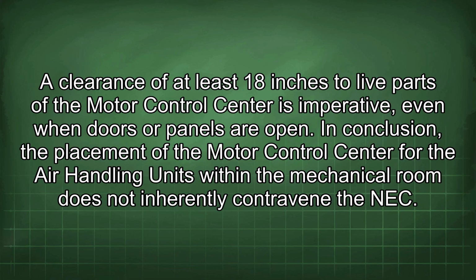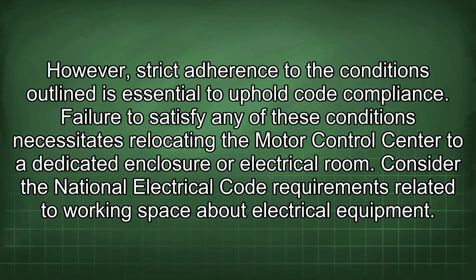In conclusion, the placement of the motor control center for the air handling units within the mechanical room does not inherently contravene the NEC. However, strict adherence to the conditions outlined is essential to uphold code compliance. Failure to satisfy any of these conditions necessitates relocating the motor control center to a dedicated enclosure or electrical room.